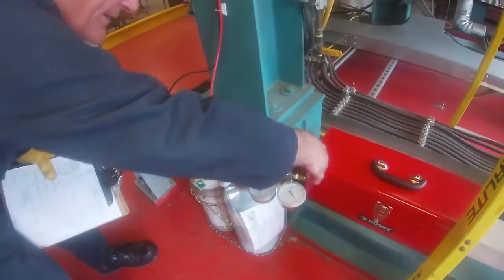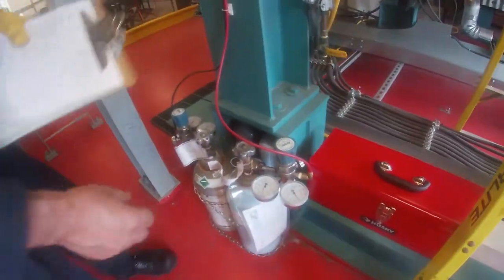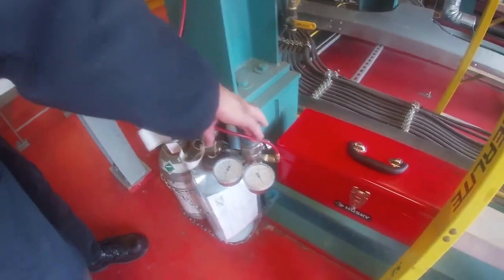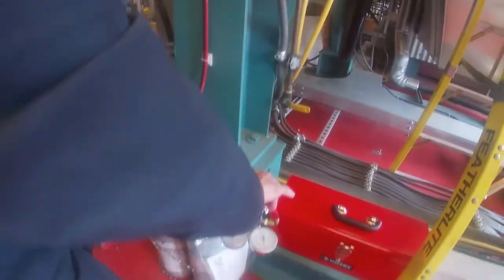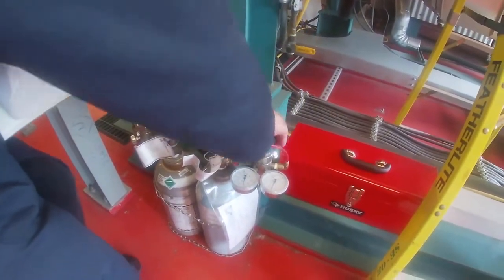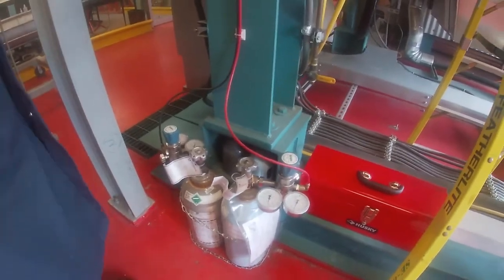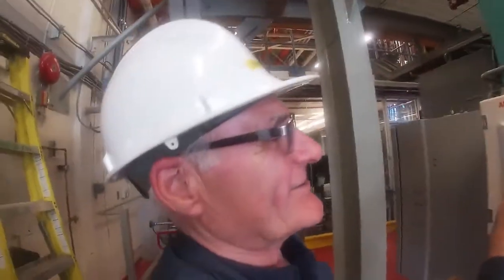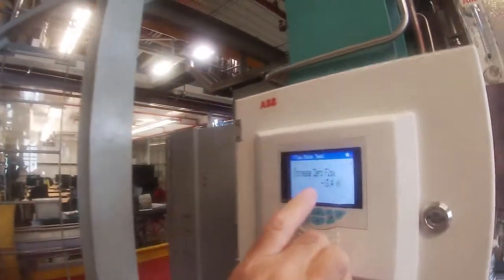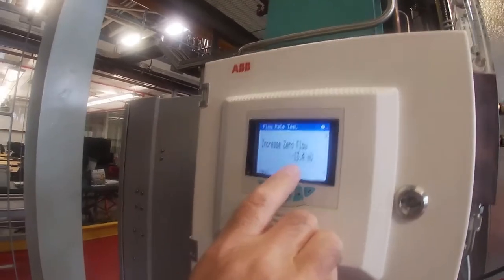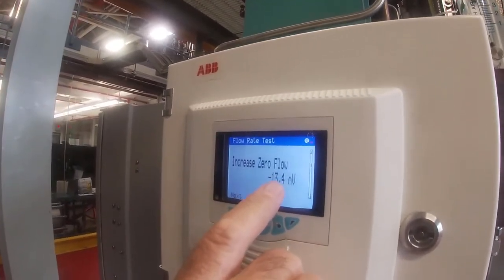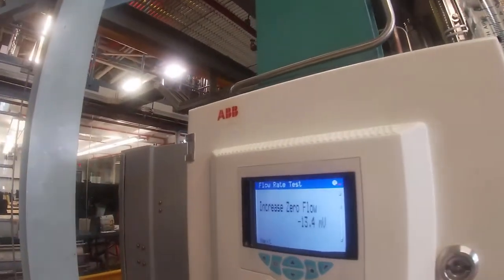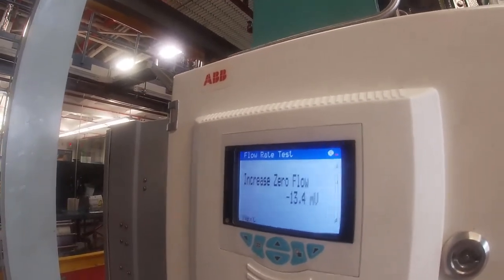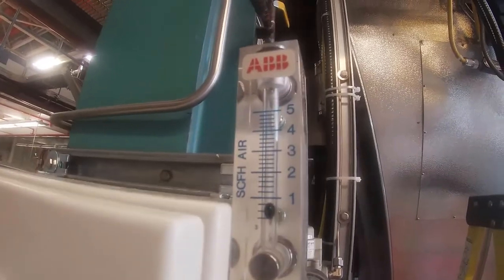Back off the regulator. Now I'm going to apply some zero gas on here. Follow instructions. Next key. So now it's going to tell me to increase the zero flow, basically until this millivolt number here stops changing. So I'm going to put some gas on, and I've got just under 1 standard cubic foot an hour.